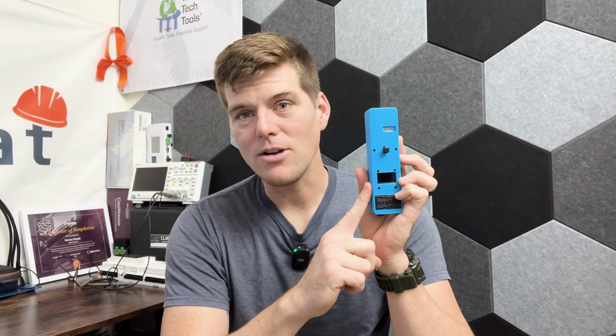If you drive that valve to 200 pulses, 300 pulses, 2,000 pulses, and then plug it back into the main board, the outdoor unit, whatever it is, the unit doesn't know where you left that valve at. So if you leave it somewhere off of 0 pulses, anything higher than that, plug it back into the equipment, turn the power back on, it's going to think that it's back at 0 pulses when it's not. And now it's going to be uncalibrated. And what happens with an uncalibrated EEV? It causes all sorts of problems in pieces of equipment.